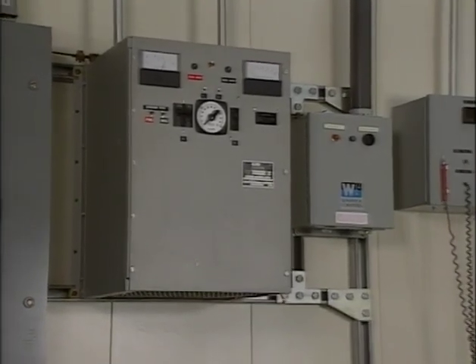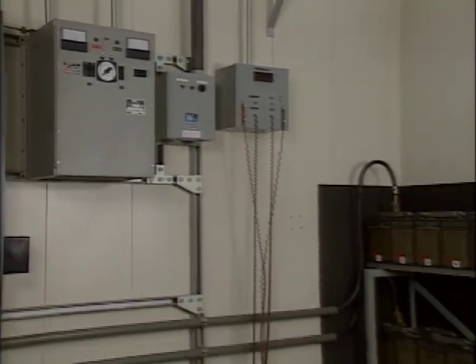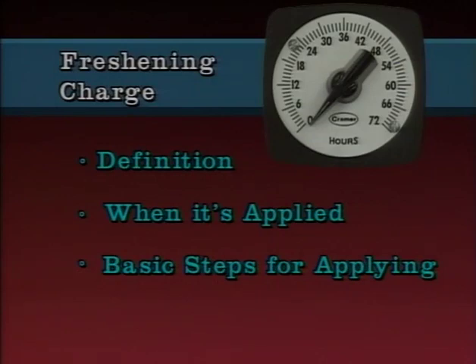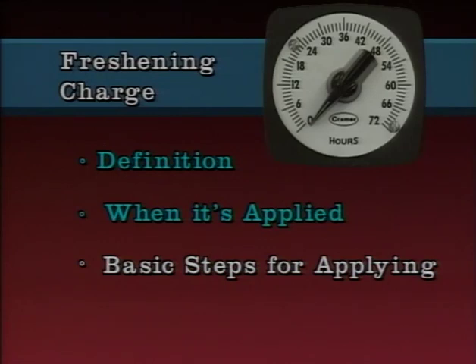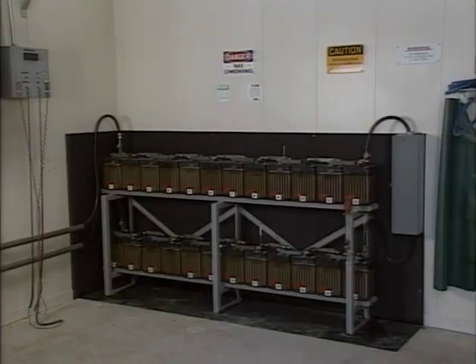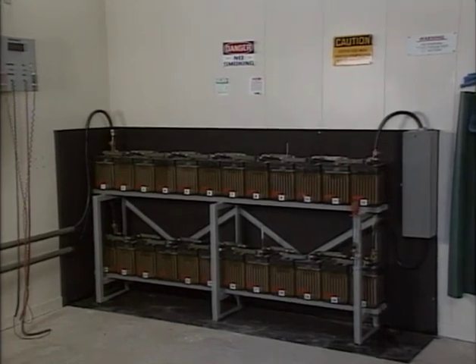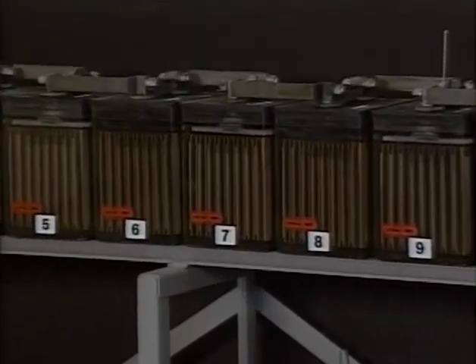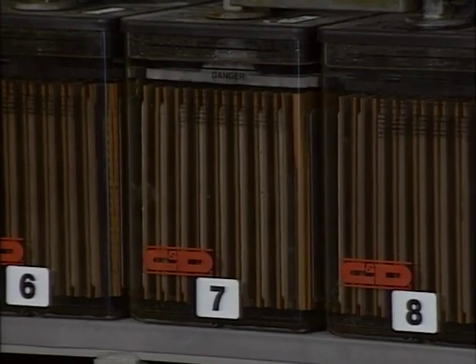One of the main functions of a battery charger is to charge a battery or a cell, but there are different types of charges that can be given a battery. This part of the program will address a type of charge called a freshening charge. A freshening charge is a charge given to new, wet-charged cells before they're put into service. Wet-charged cells are new cells shipped from a manufacturer already filled with electrolyte and fully charged. Although wet-charged cells are fully charged when they leave the factory, they will gradually self-discharge until connected to a source of voltage higher than their open-circuit voltage.